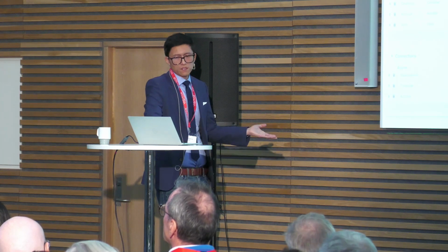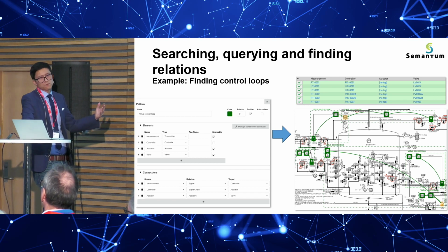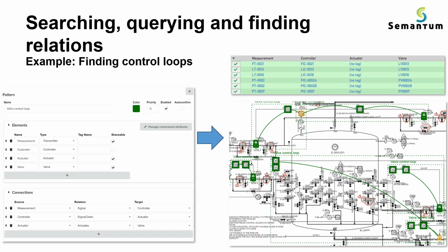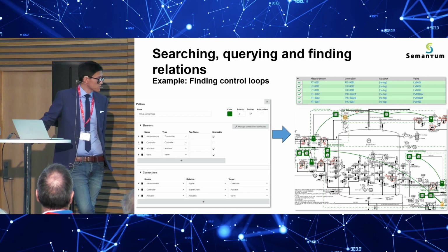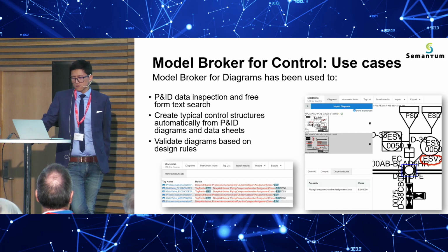We're asking that tool to give us a table of these components so that we can then use this table and create in the control application software the equivalent. So it is a way to create these stabilizing control loops defined on the P&ID automatically. This tool supports right now some simulation systems and also some DCS systems. But the idea is simple, and I think many DCS are following the same idea, that these are defined as tables. So you can imagine that this can also be extended to other DCS systems.